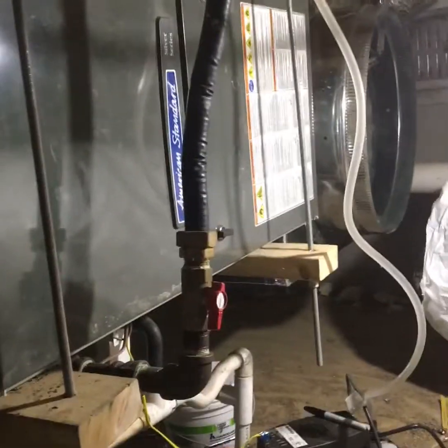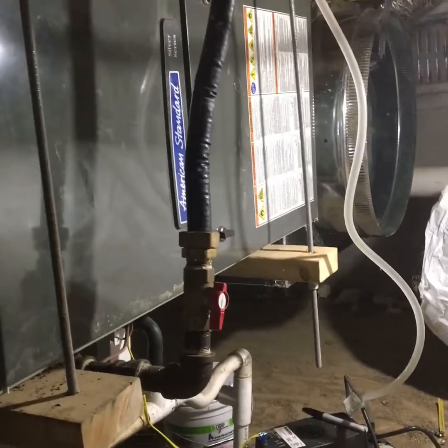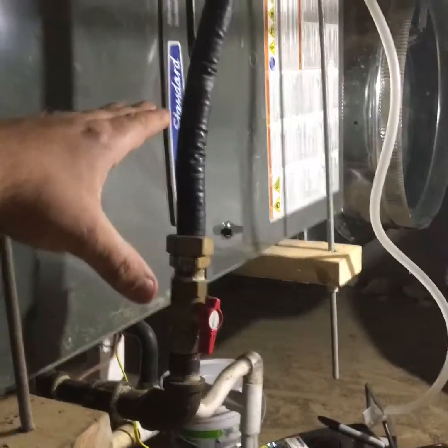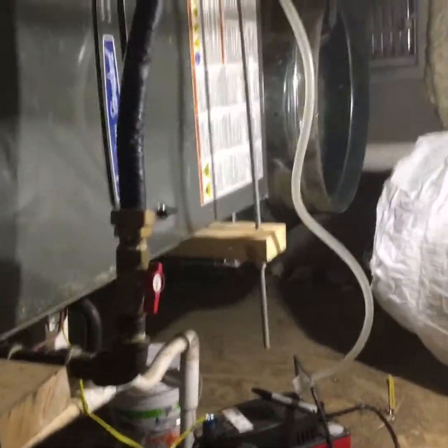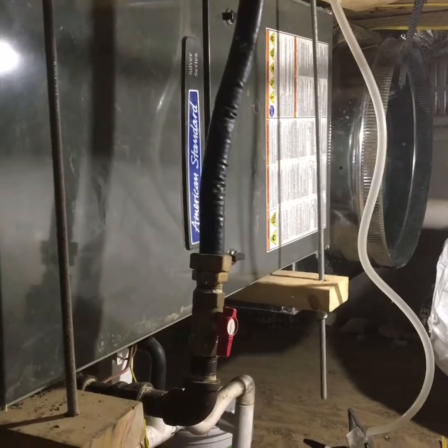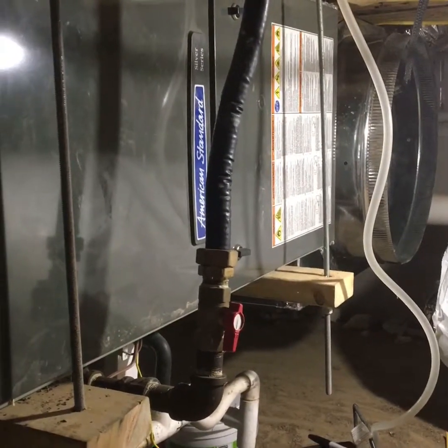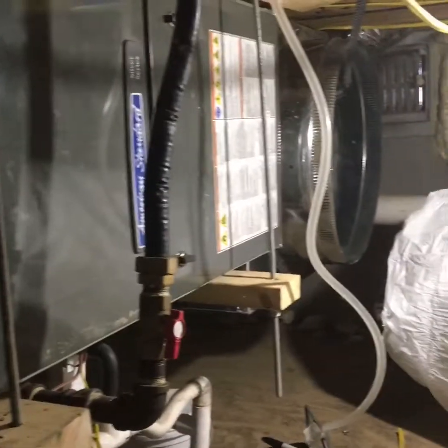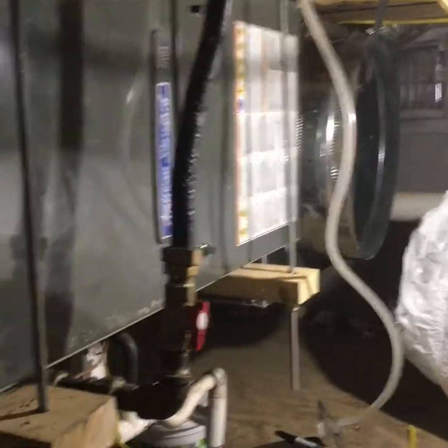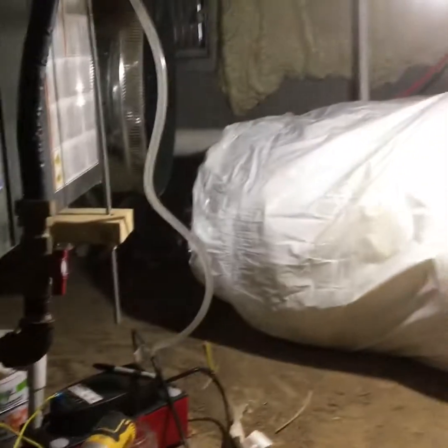Another unit, I'm not sure if it was the same company or not, but they ran their line sets right in front of these doors over the evaporator. So now when you have to pull that blower motor out, you're going to have to cut into the refrigerant system, pull the vacuum, I mean, it's just going to be a nightmare. So think about the poor service technicians when you're installing units. Anyway, but that is it. We'll get this guy back up and going.